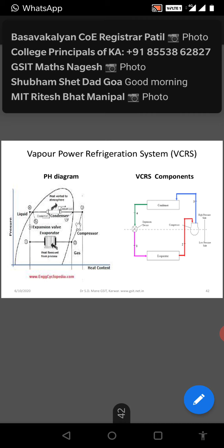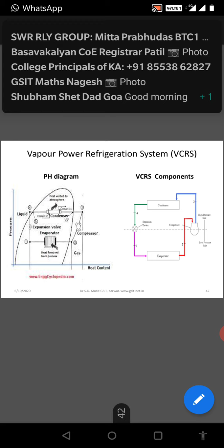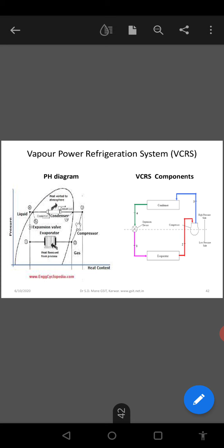So you can see the pressure enthalpy diagram to the left, where all the 4 components are shown physically also. Like 1 to 2 is the evaporator, then 2 to 3 is the compressor work, 3 to 4 is the condenser work. The condenser work involves evaporator work plus compressor work. And last, 4 to 1 is the expansion valve, where you can see the pressure is reduced, and because the pressure is reduced, temperature also gets reduced.